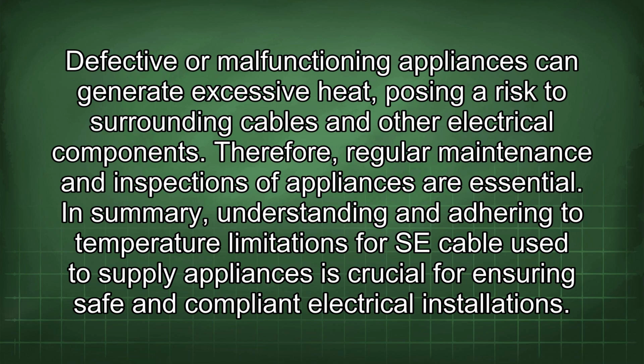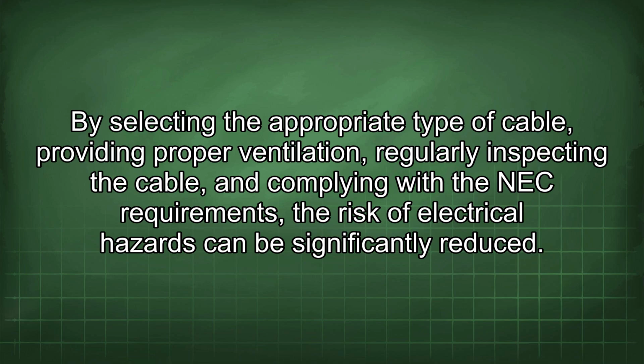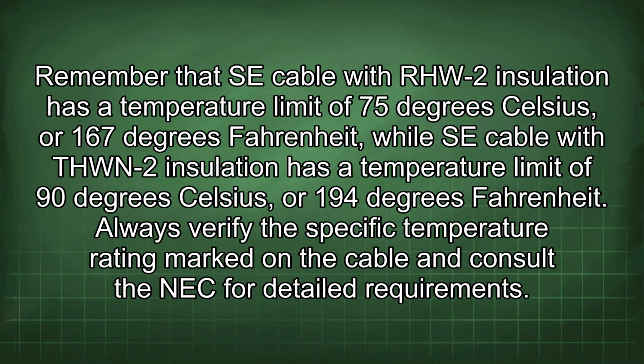In summary, understanding and adhering to temperature limitations for SE cable used to supply appliances is crucial for ensuring safe and compliant electrical installations. By selecting the appropriate type of cable, providing proper ventilation, regularly inspecting the cable, and complying with the NEC requirements, the risk of electrical hazards can be significantly reduced. Remember that SE cable with RHW-2 insulation has a temperature limit of 75 degrees Celsius or 167 degrees Fahrenheit, while SE cable with THWN-2 insulation has a temperature limit of 90 degrees Celsius or 194 degrees Fahrenheit. Always verify the specific temperature rating marked on the cable and consult the NEC for detailed requirements.